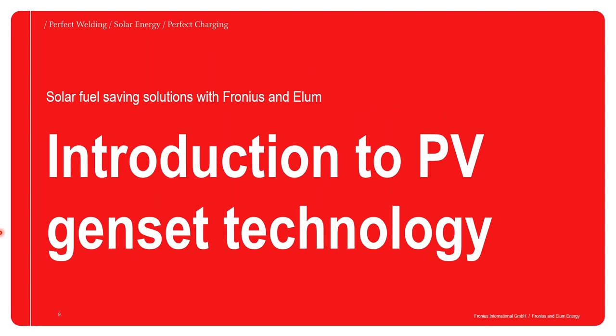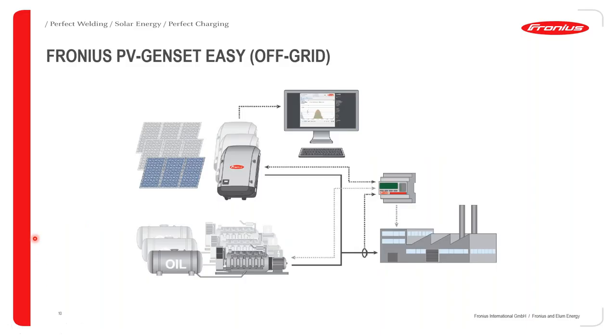The Fronius PV genset easy solution is a completely off-grid system comprising Fronius inverters, a diesel genset, a Fronius PV controller, and the consumer load. The Fronius inverters convert DC from panels into AC which is sent to the load. A CT detects the amount of power the load is drawing and sends this information to the PV controller, which then controls the Fronius PV inverters. More detail on this will follow later in the slides.